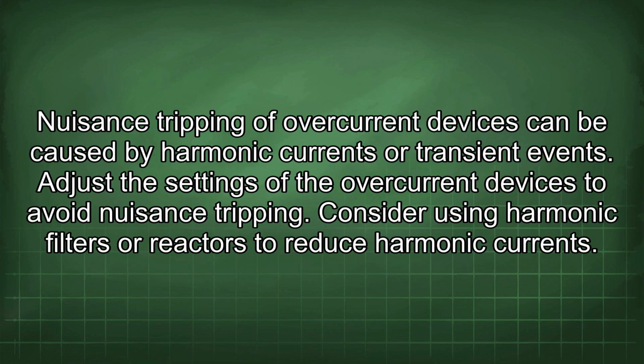Nuisance tripping of overcurrent devices can be caused by harmonic currents or transient events. Adjust the settings of the overcurrent devices to avoid nuisance tripping. Consider using harmonic filters or reactors to reduce harmonic currents.